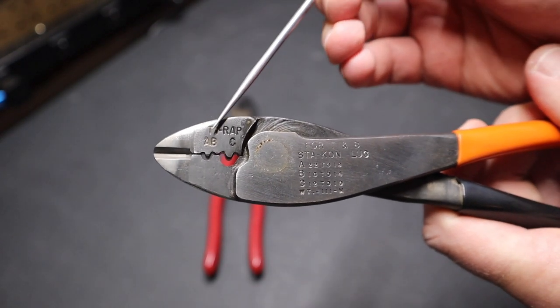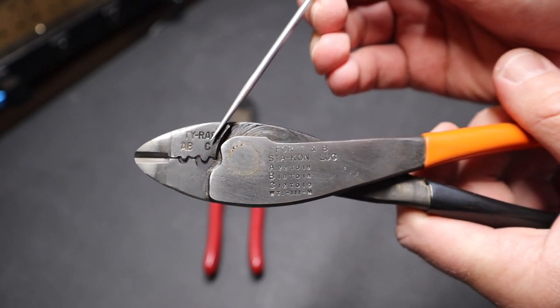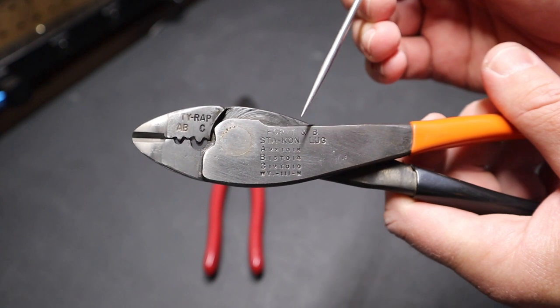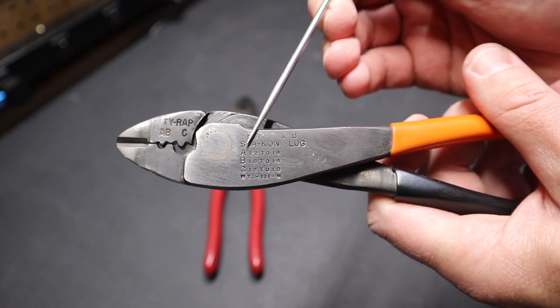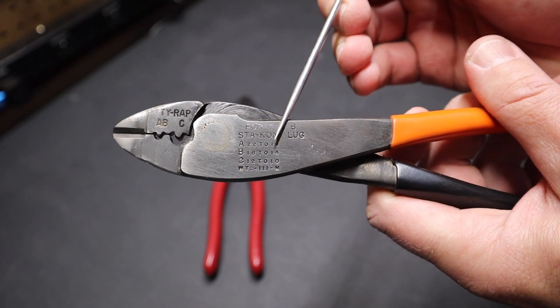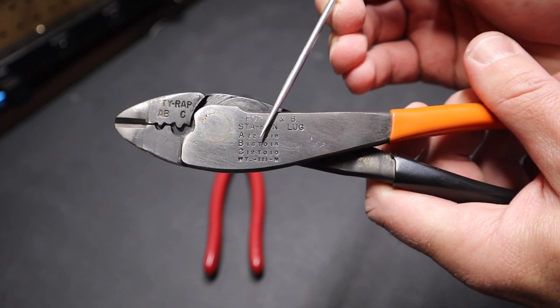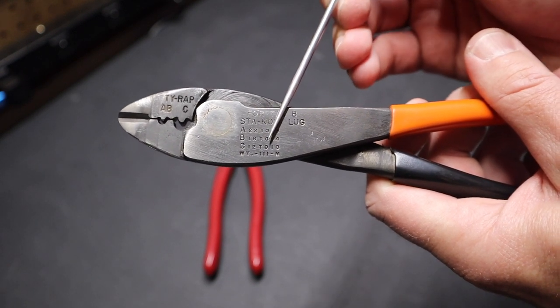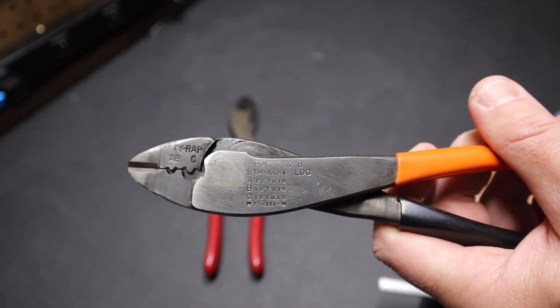You'll see here, they have a label on the side of the tool. They have A, B and C for different parts. And here they define what they do. A part of the crimper can do 18 to 22 gauge. B can do 16 to 14. C can do 12 to 10 gauge. So that's how that's laid out.